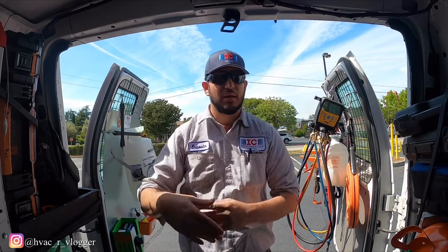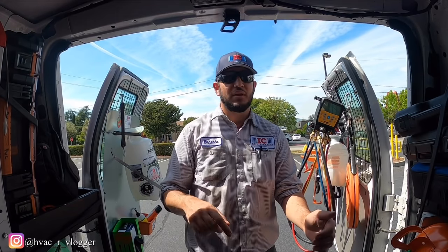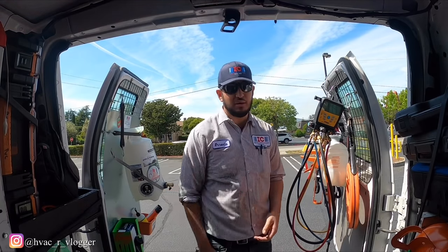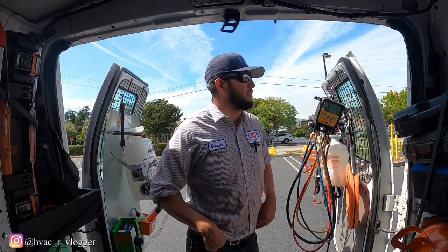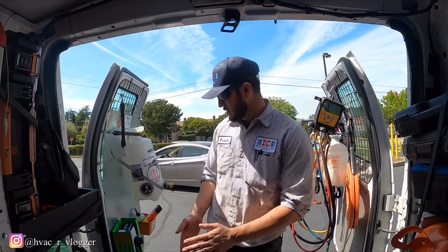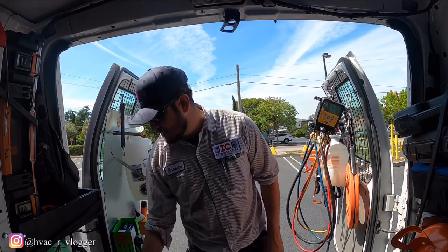It's a flapping one. Also, if you guys notice, whenever I was hitting it, the LED on the board wasn't turning on and off, on and off. So basically it's a bad bin control. Like I explained to the manager, I'm gonna leave the unit on, but it's gonna shut off randomly. We don't know when or why. So she understands. And yeah, that was pretty simple.